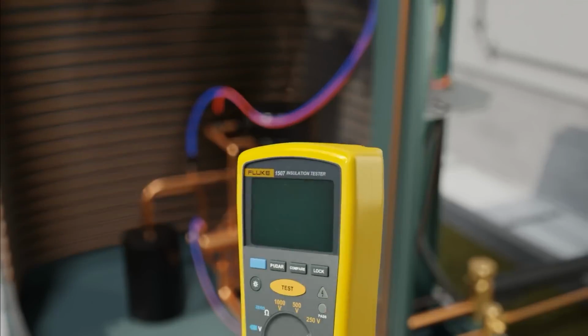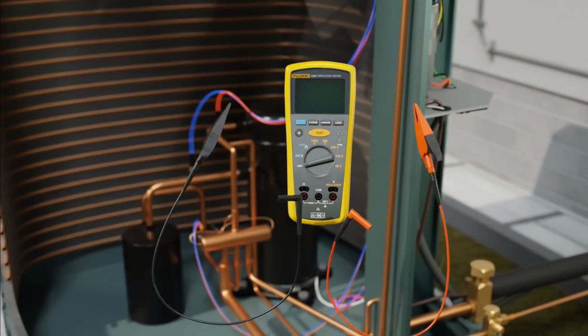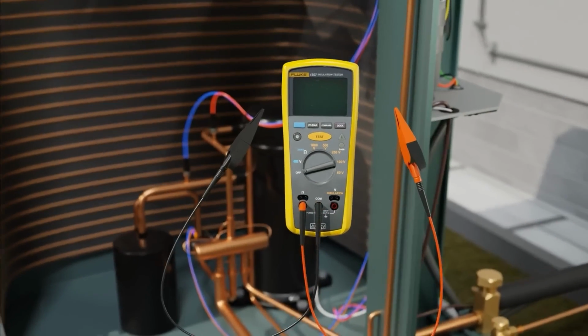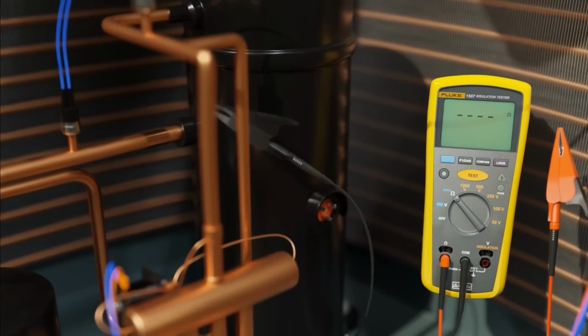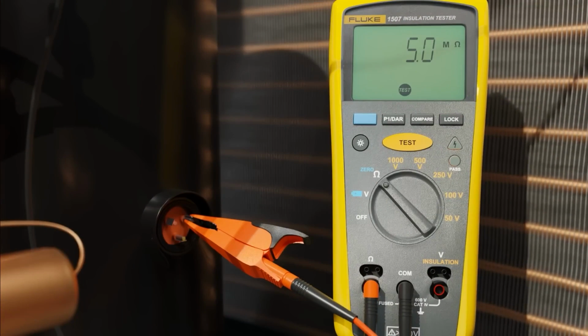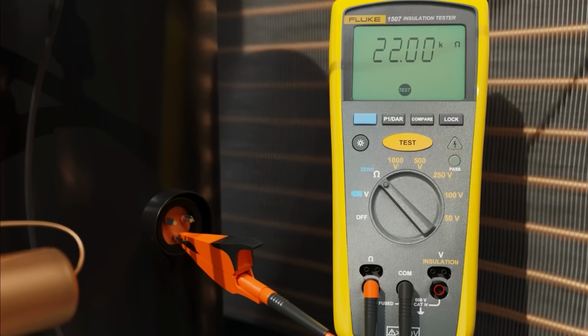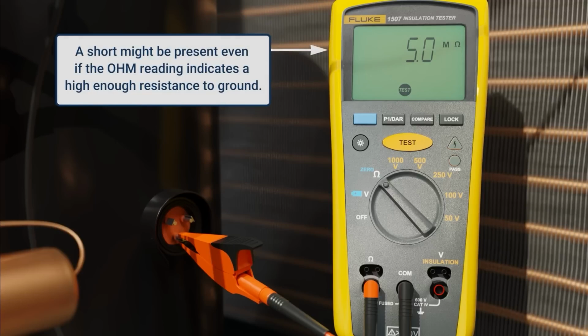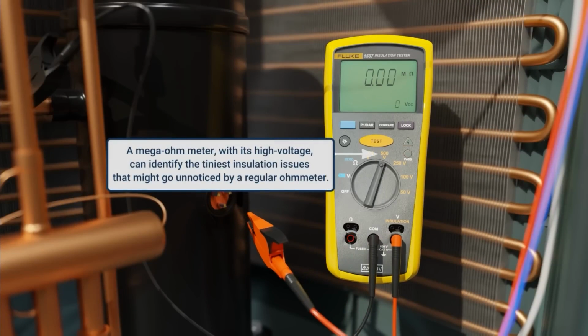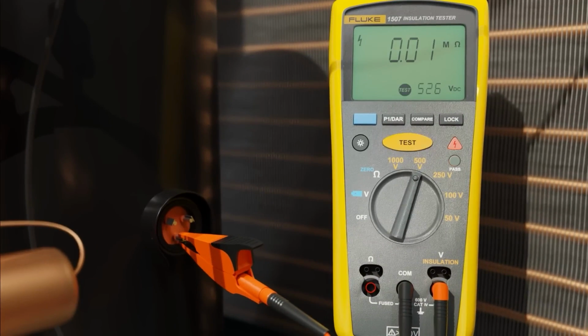Anyway. The right way to do a safety check is to check from leg to ground, okay? The reason is because there are cases where you will measure 0 volts, but there will still be voltage to ground. We see this a lot, actually, whenever you have a breaker that's failed and you only have one leg, and you measure and you're like, oh yeah, I got 0. So that's the right way to do a safety check, is to ground.